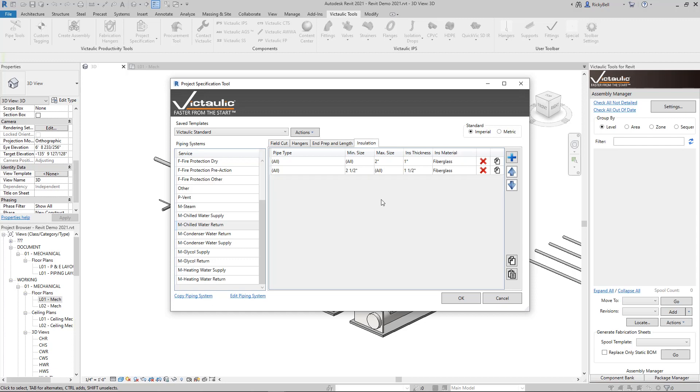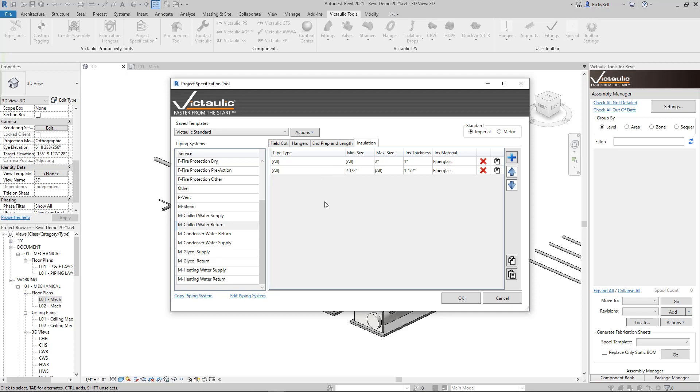When it comes to insulation, this is an area where you can set up rules. You can get as granular as you want by putting in specific pipe types. In this case, we just have a minimum and maximum size. Anything over two and a half inch is going to get an inch and a half of fiberglass insulation. Anything under two inch will get one inch.